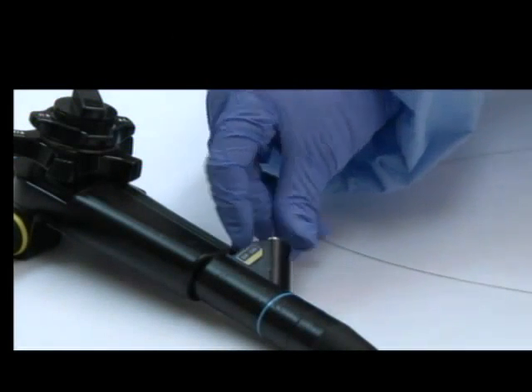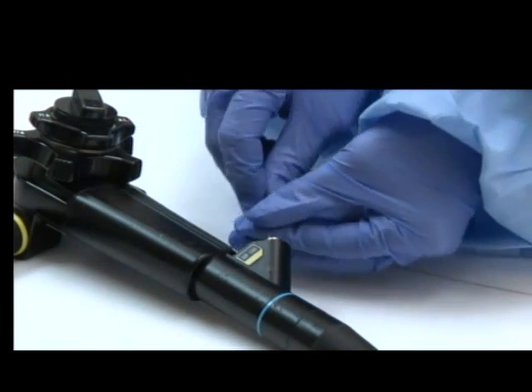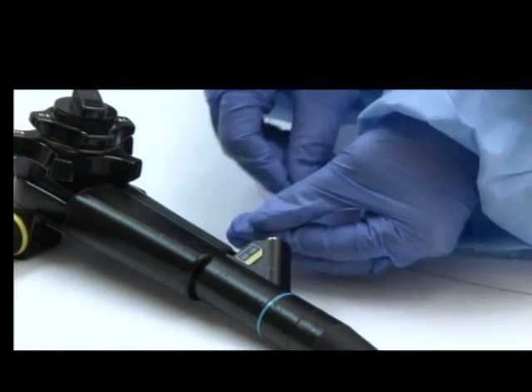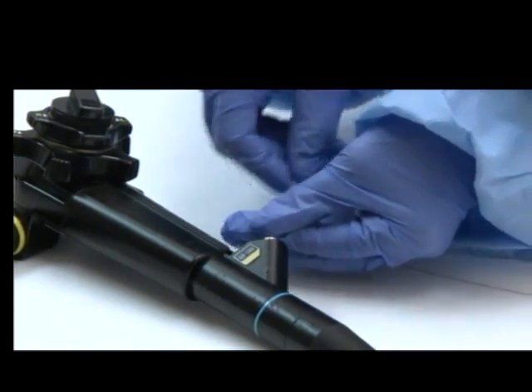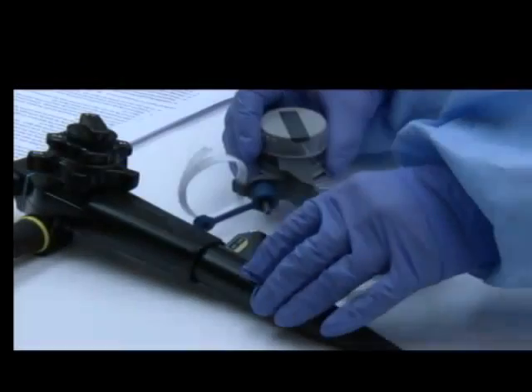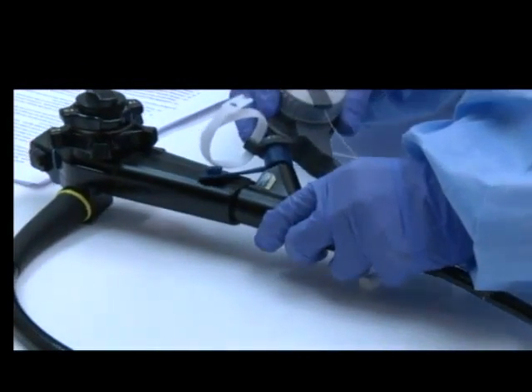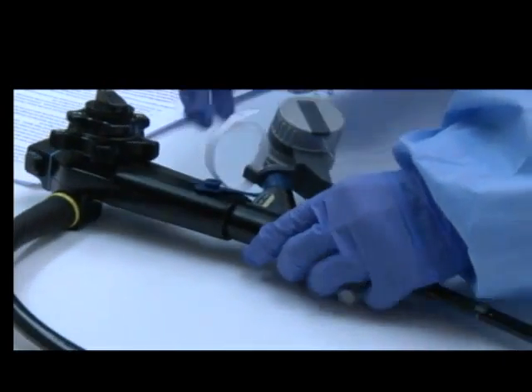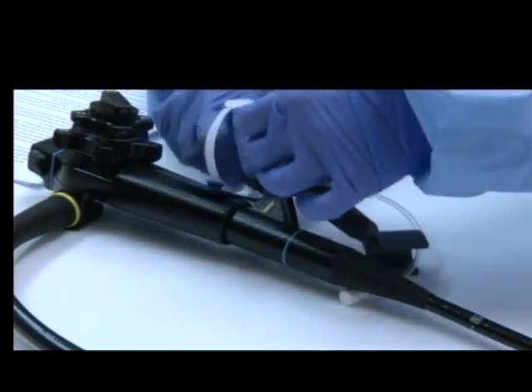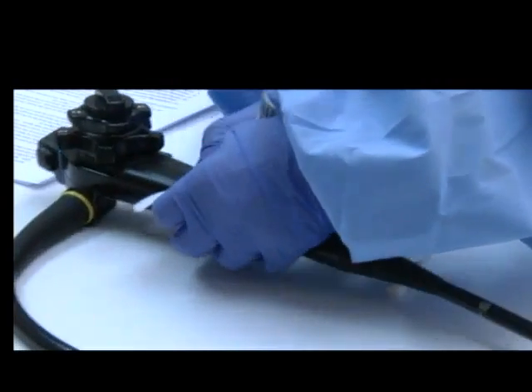Insert and advance the trigger wire completely through the biopsy channel. Ensure that the looped end of the trigger wire extends approximately 5 centimeters from the distal end of the endoscope. Attach the biopsy valve and handle to the biopsy port on the endoscope. Ensure that the plastic stem of the handle seats well within the valve.